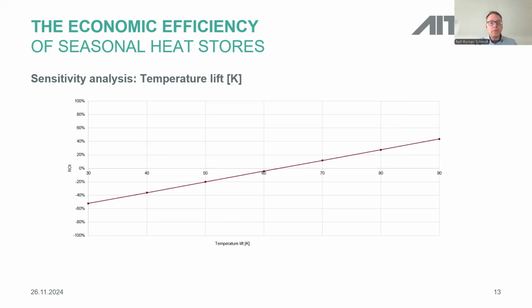Very much important is this temperature lift as well. And I think that's very interesting for me. Again, in the reference case of 60 Kelvin temperature lift, it's not economic, but if you go for the 30, if you would have a return line of 60 degrees temperature, you can charge your storage up to 90, you have 30 Kelvin delta T. That reduces your economic efficiency very much. However, on the other side, if you're able to boost that up to 90 or higher by, for example, reducing the return or the lower part of the storage temperatures to only 10 degrees maybe, or boosting the upper part of the storage to 140 degrees, you're increasing your economic efficiency a lot.